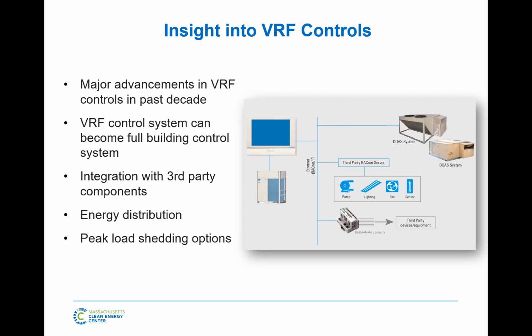Go ahead. That's a good question. The question is, how does energy distribution work with heat recovery? So what I'm going to do is compare it to how people do tenant metering or tenant billing with water source heat pumps. Usually with water source heat pumps, it's great because that heat pump in the suite, that vertical stack heat pump, is powered by the suite owner. So that owner pays for that compressor that's running. What the house pays for is, in the middle of summer, the cooling tower or the boiler.